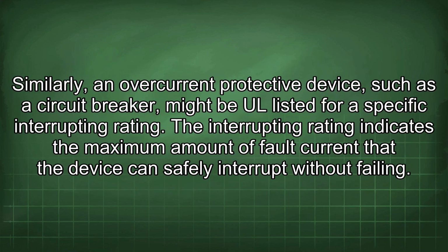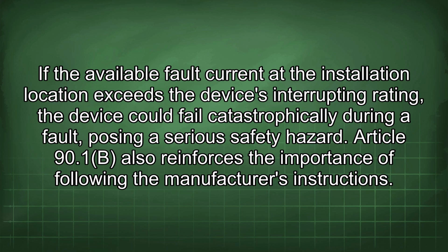Similarly, an overcurrent protective device, such as a circuit breaker, might be UL listed for a specific interrupting rating. The interrupting rating indicates the maximum amount of fault current that the device can safely interrupt without failing. If the available fault current at the installation location exceeds the device's interrupting rating, the device could fail catastrophically during a fault, posing a serious safety hazard.